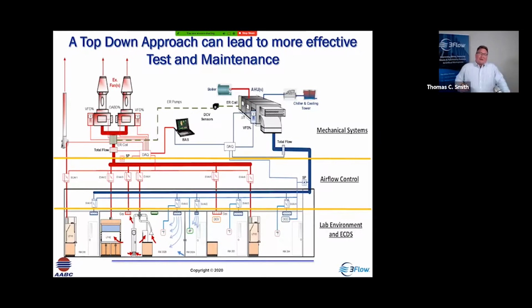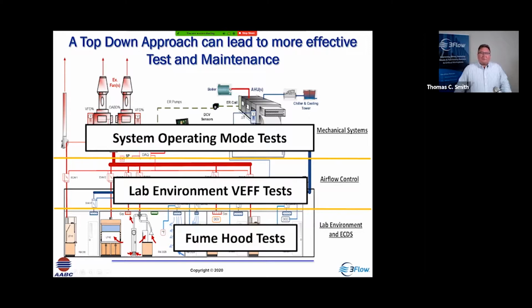So we have to take a top-down approach. We don't want to start testing the fume hoods until we know the exhaust fans are working properly. So looking at a top-down approach, we start with the system test first, then the lab, then the fume hoods. So there's a sequential path. And we have found that this will solve many problems and will reduce the time on site because we have a reduction in the duplicative work of test the hood, fix the fan, retest the hood, and so on.